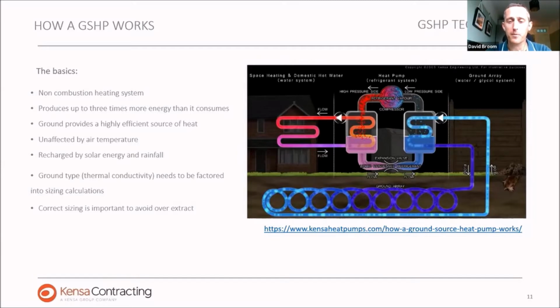The key with the heat pump is that the difference in temperature between where the energy starts from, the ground, and where you're putting the energy into, either radiators or domestic hot water, matters: the closer those two temperatures are, the less work you have to put into the compressor and the more efficient it becomes. The general reason heat pumps are a good idea is that for every kilowatt of electricity you put into that compressor, you get 3 to 4 kilowatts of heat delivered into the building. That's where the COP, or SCOP, or efficiency of 300 to 400%, comes from - that ratio of energy in to energy out.